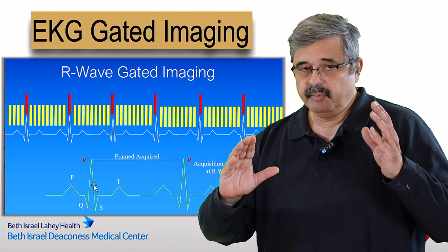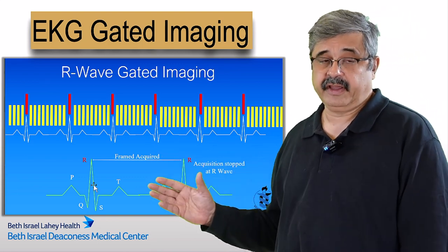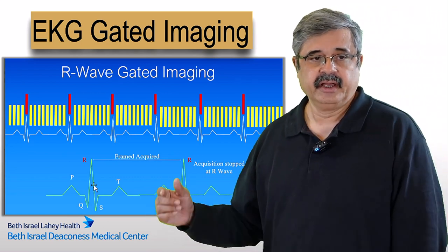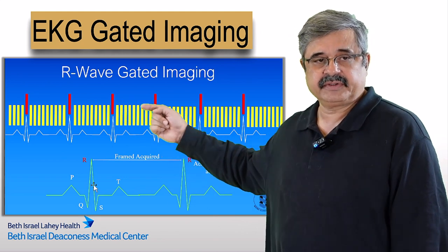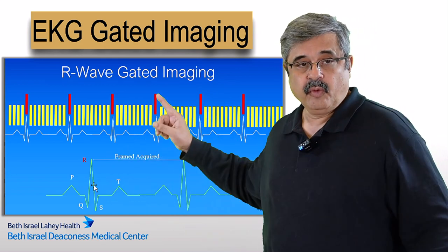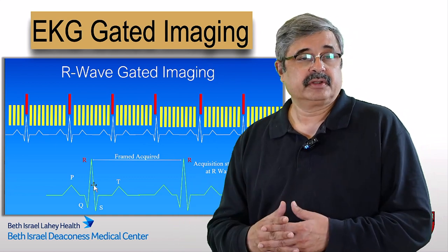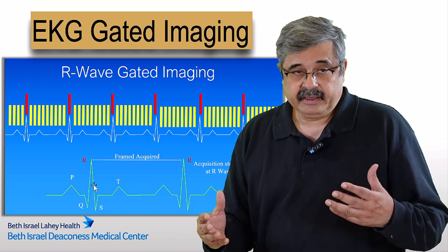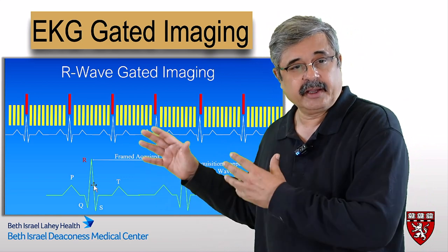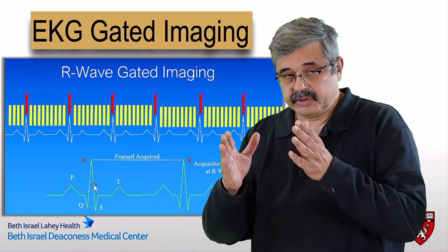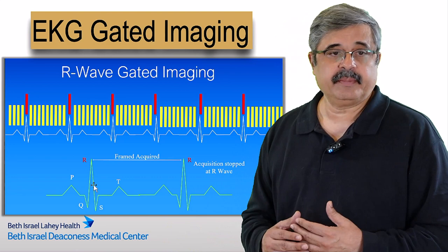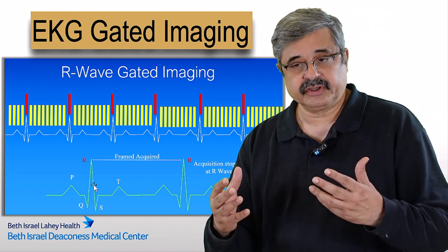The most important thing to recognize is that a regular R-R wave interval and normal sinus rhythm were absolute requirements for this form of imaging. The number of frames between two adjacent R waves had to be absolutely equal so they could be put together. If one interval had more or fewer frames than the other, you'd have temporal dyssynchrony. Additionally, you had to keep the probe still, prevent patient movement, and acquire images over a minute or so with a regular heart rate — a lot of conditions that all had to be satisfied simultaneously.